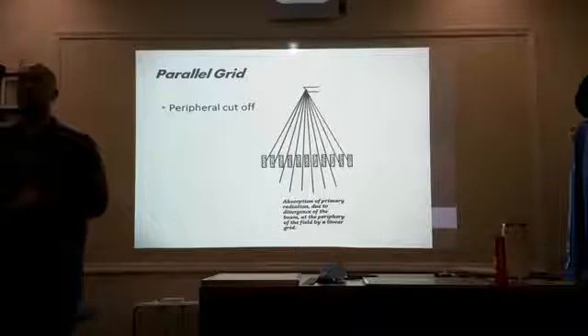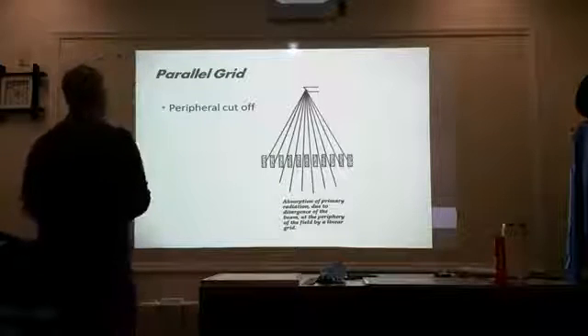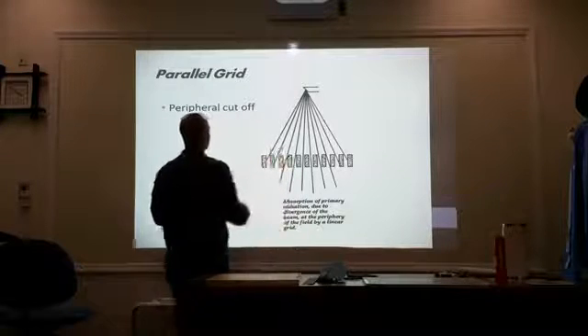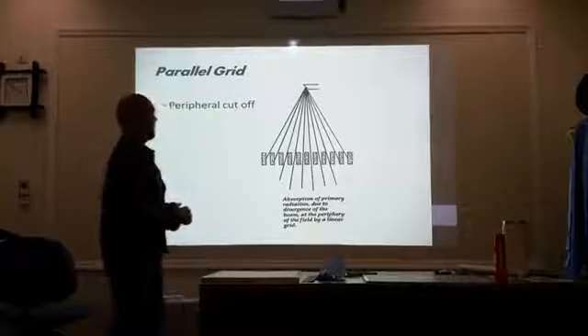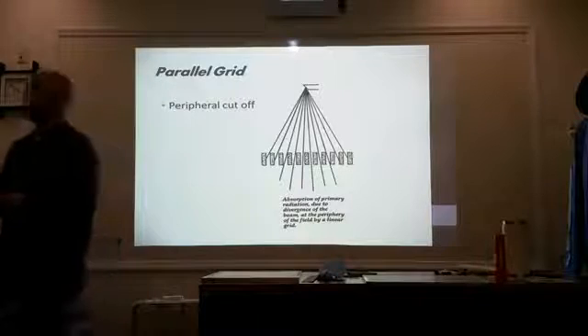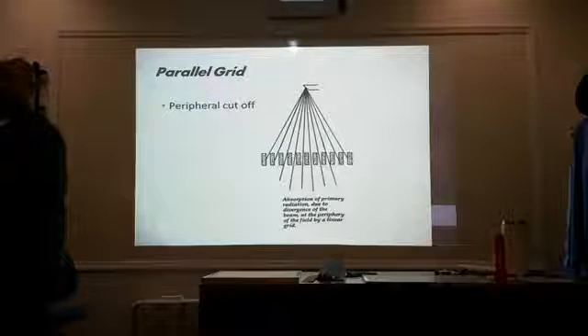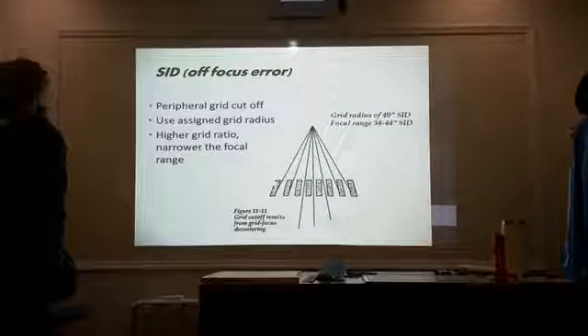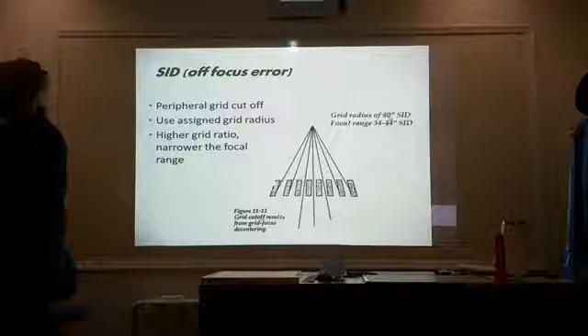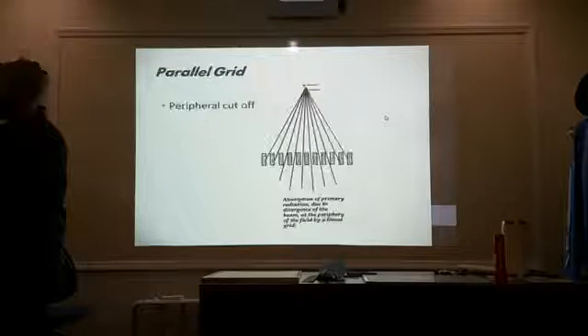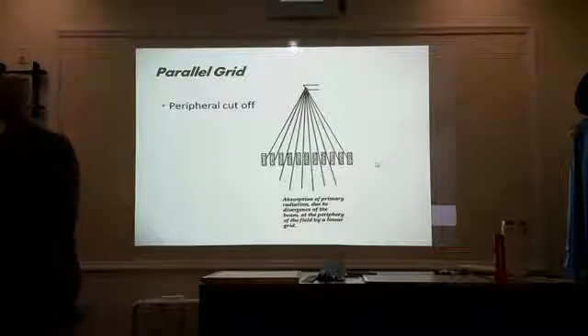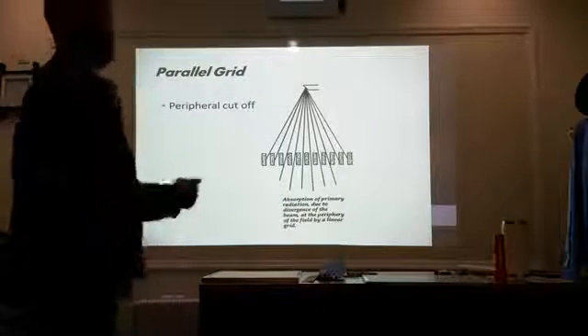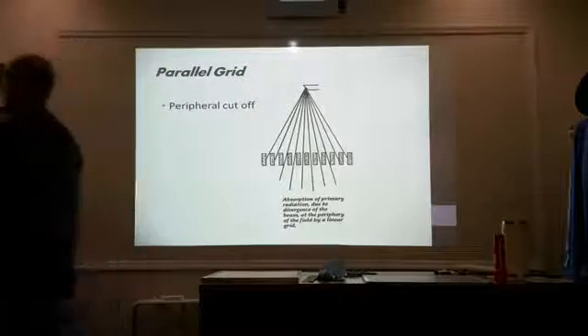And then we have the parallel grid. Non-focus grid, the strips are upright. You're going to have peripheral grid cut off if you don't match your grid radius. Remember your grid radius? Grid radius is right here, your suggested SID. So with this parallel grid, you should match the grid radius. If they say 40, try to stay as close to 40 as possible.